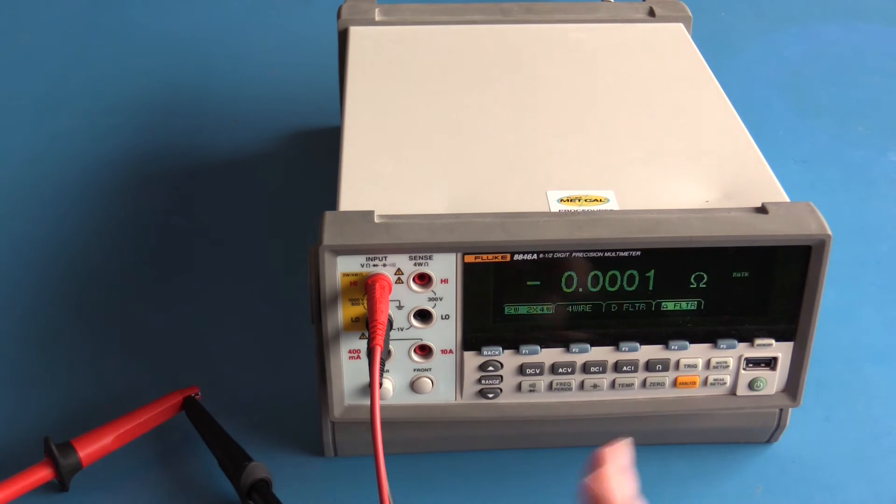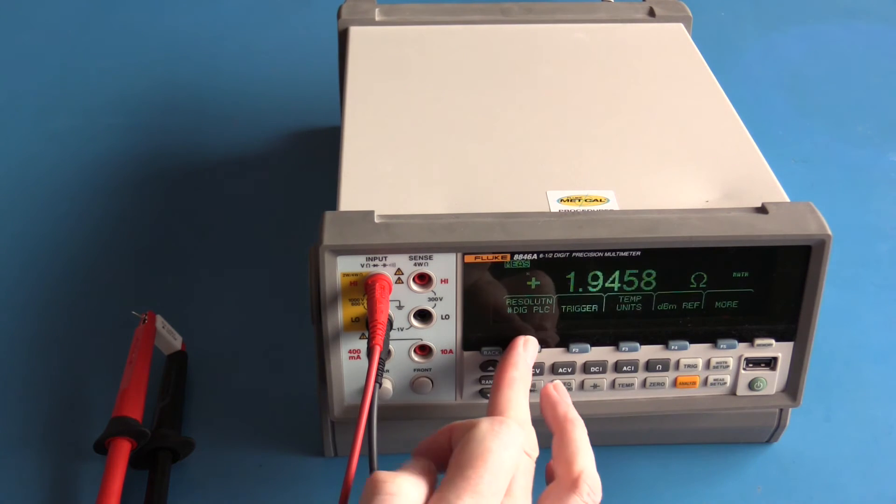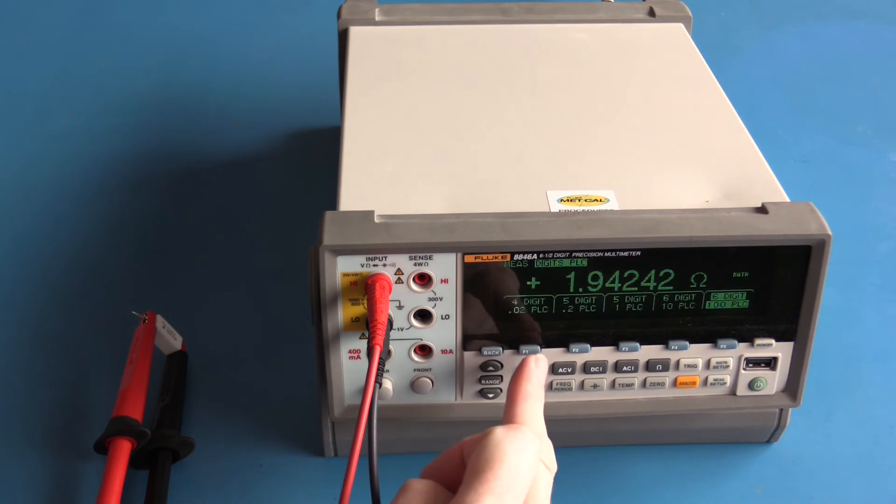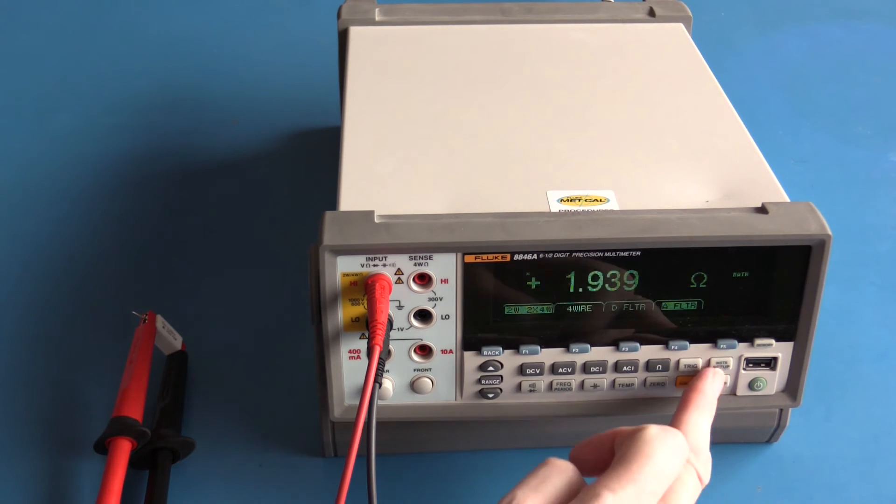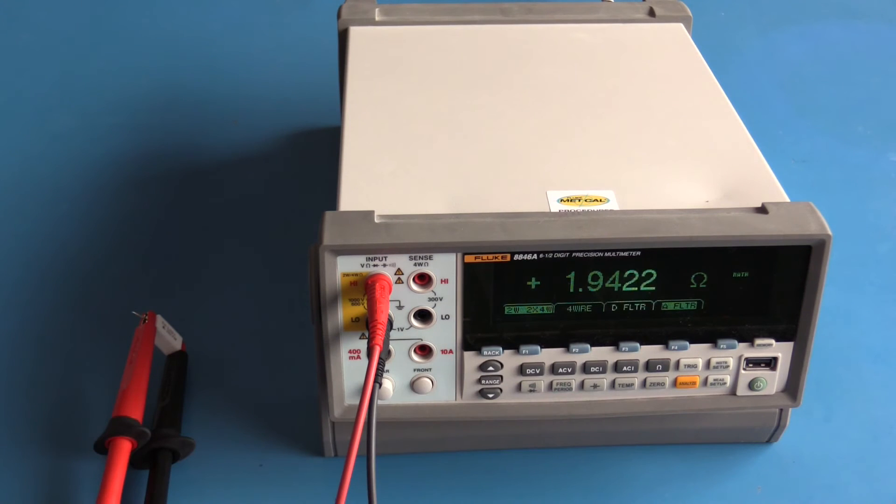I'm fairly happy with that. We're measuring this 2.2 ohm resistor right around 2 ohms. I'm going to increase the measurement resolution. By increasing the resolution I have slowed down the measurement considerably. I'm now going to change to the lowest resolution. My update rate now is very very quick. I'm now going to change back to my preferred five and a half digit resolution.